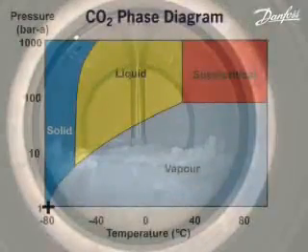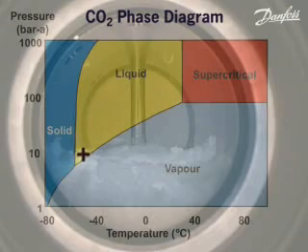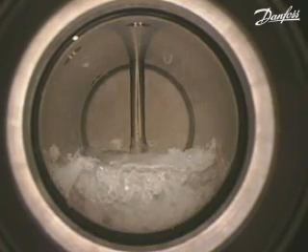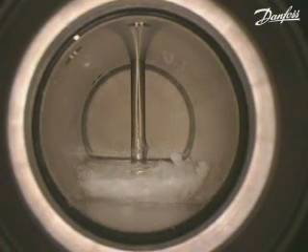Solid CO2 is also known as dry ice. It has a surface temperature of minus 78.4 degrees C at standard atmospheric pressure. The pressure inside the cell is now approximately equal to the surrounding atmosphere of 1 bar absolute. The vent valve is closed. The entire cell is now below ambient temperature and will absorb heat from the surroundings. Triple point conditions are re-established as the solid CO2 melts and as the pressure and temperature rises, the cell contains liquid CO2 and vapour in equilibrium.